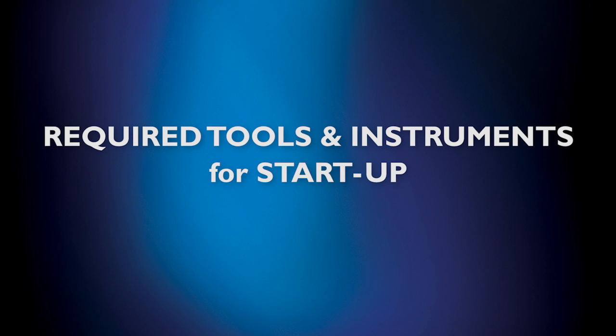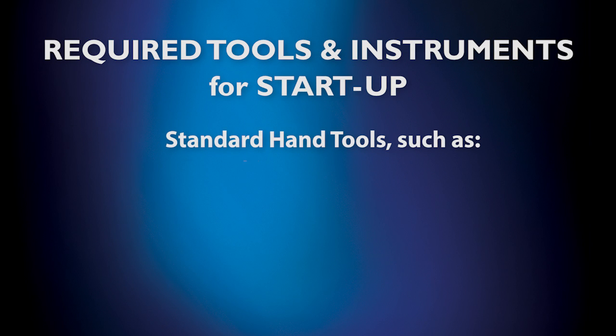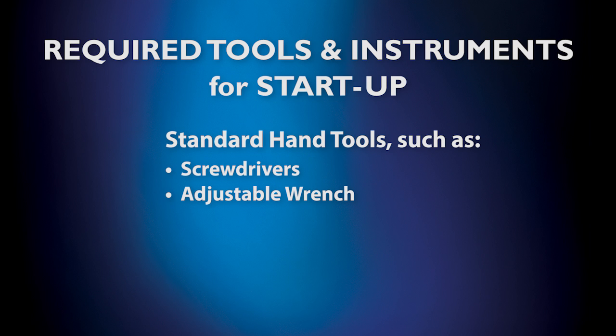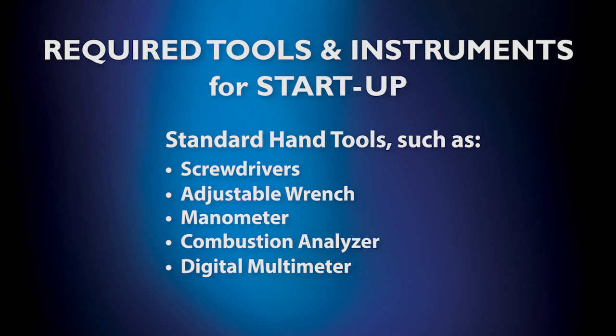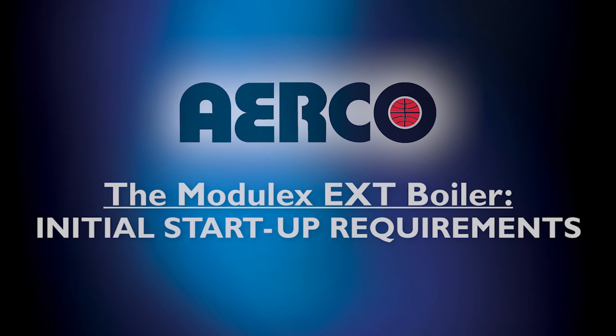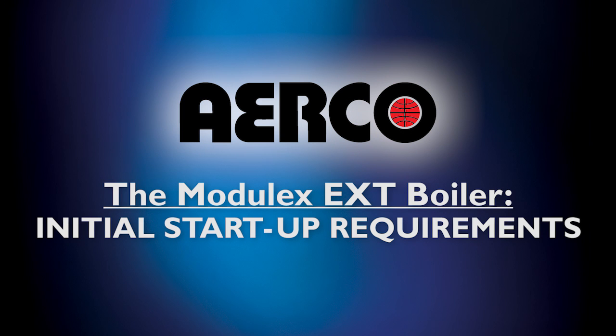Before we begin showing you all the necessary startup procedures, please review this list of important equipment and instruments that you'll need. Standard hand tools such as regular and Phillips head screwdrivers, an adjustable wrench, a manometer that is capable of reading both positive and negative pressures, a combustion analyzer, a digital multimeter, metric Allen wrenches. Please remember to carefully inspect all gas, water, venting, and condensate lines to make sure they are installed according to the specifications outlined in your manual.